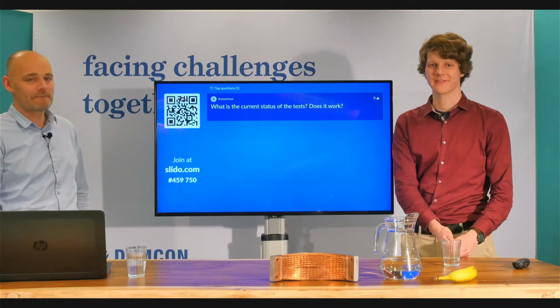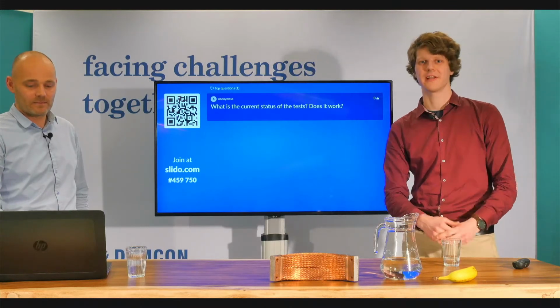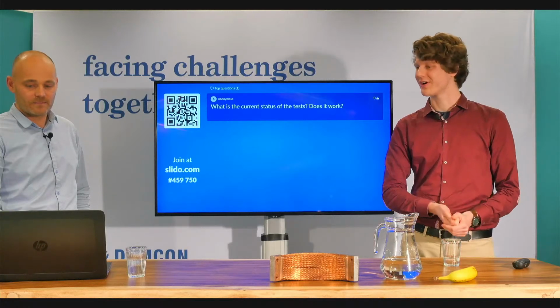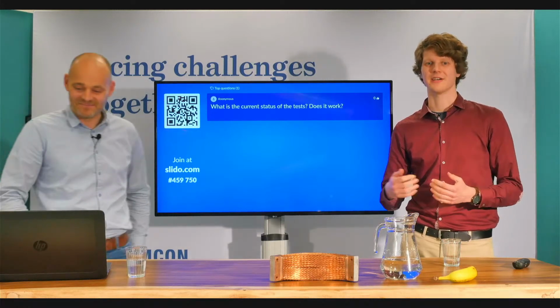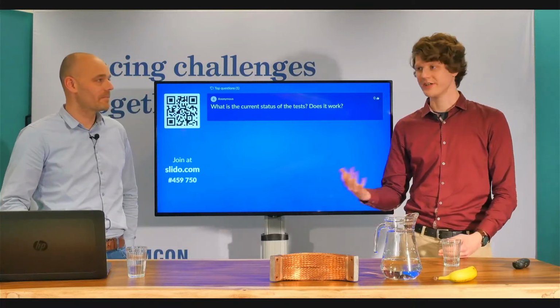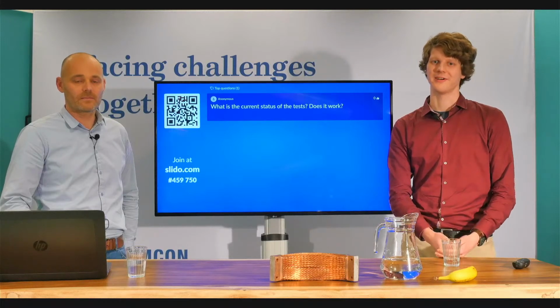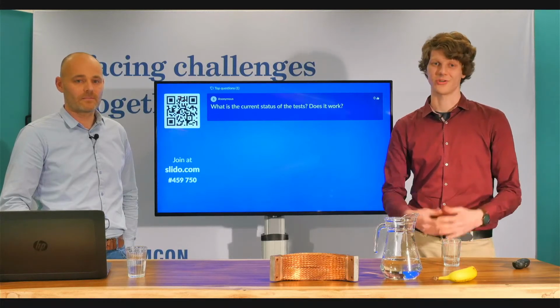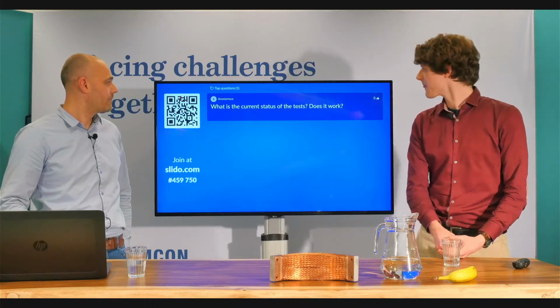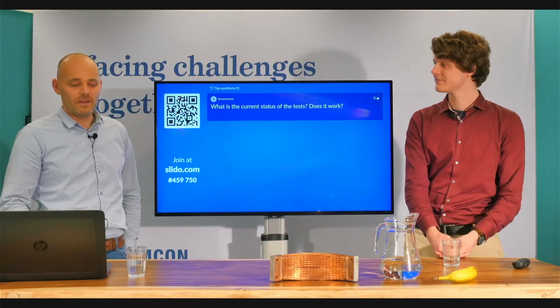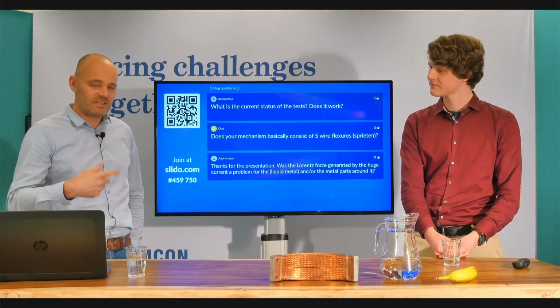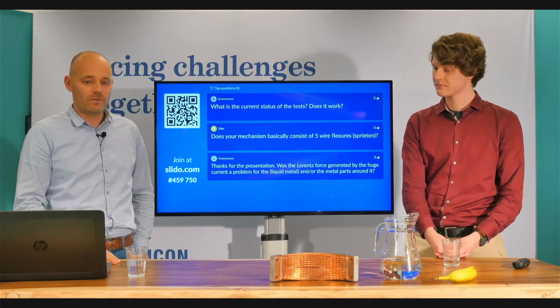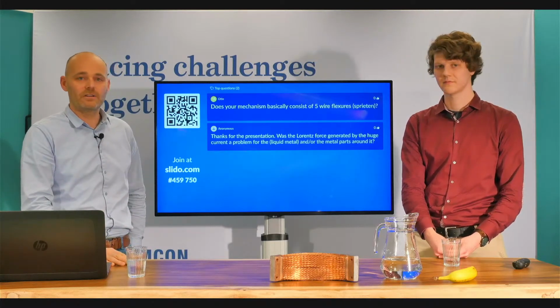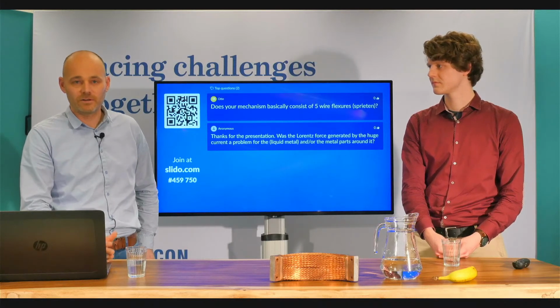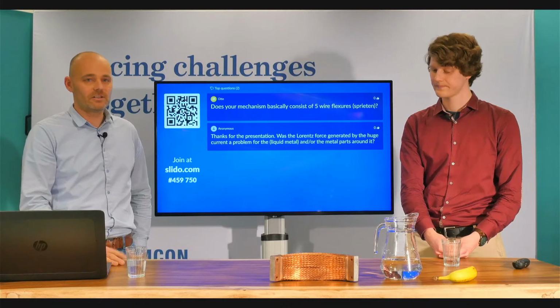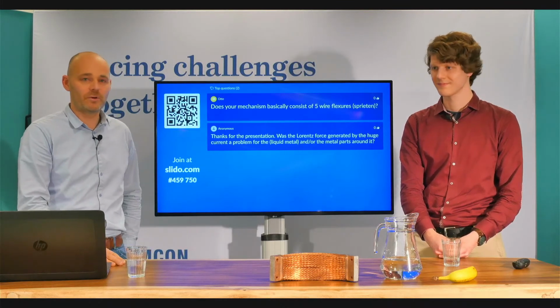Yeah, so the current state of the test: right now we're in the implementation phase in the lab. A lot of the components we showed you are together, and we are testing the first functionalities, including the heaters we mentioned and the power supply. But we're not yet testing the whole system together. It's also nice to tell that the initial test runs with the current have been done. So we're not going max right away. We tested with 10% current, which means a 1% actual heat load, but still a reasonable 1300 amps we put through the component.